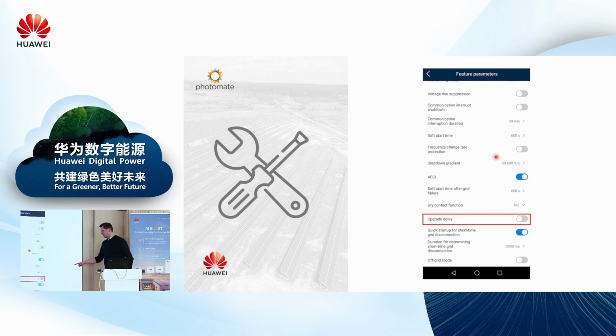Upgrade delay. This is a function which is enabled by default, and my suggestion to you as installers, or for your installer crews, is to disable it. Here is why. In Huawei systems, it's super important to have the latest version of the firmware installed. That's why you're supposed to always have some firmware packages downloaded on your memory when you're going on site. But upgrade delay allows you to upload the package of the firmware to the equipment and store it until the moment when some conditions will allow the upgrade.